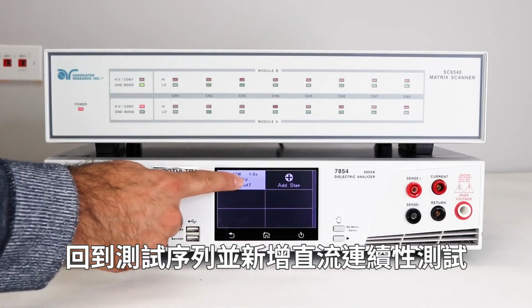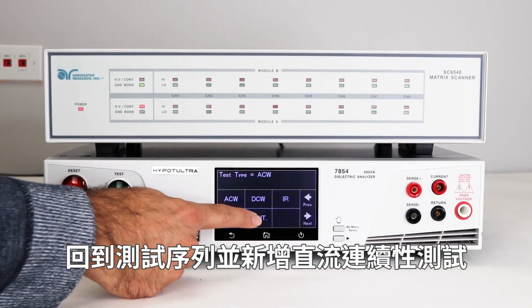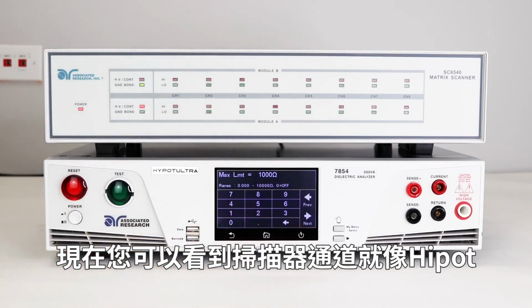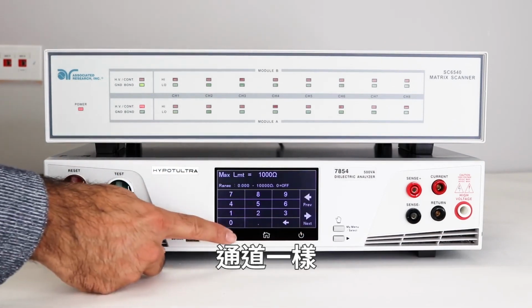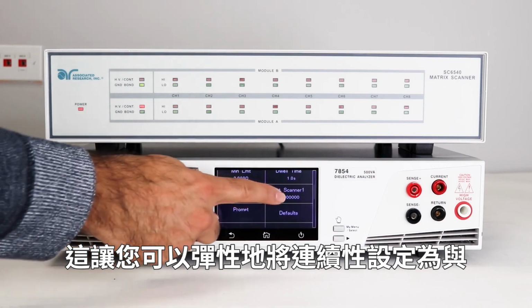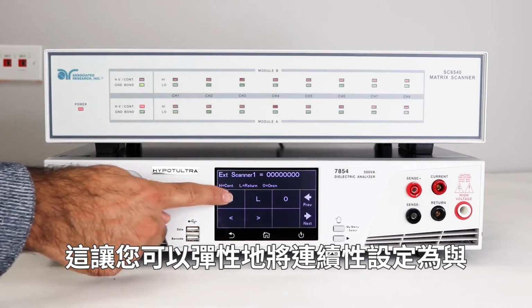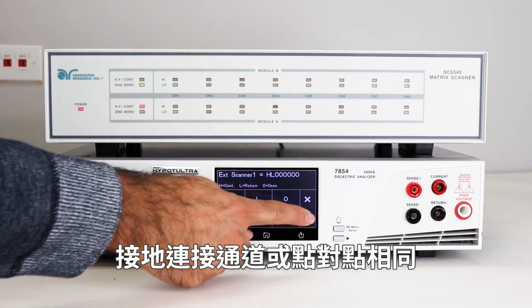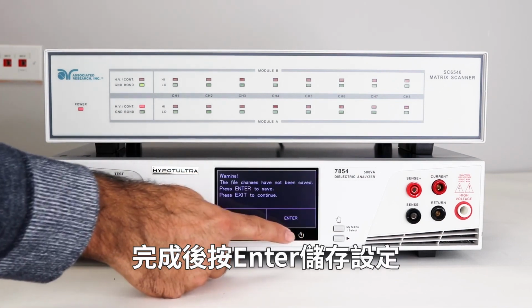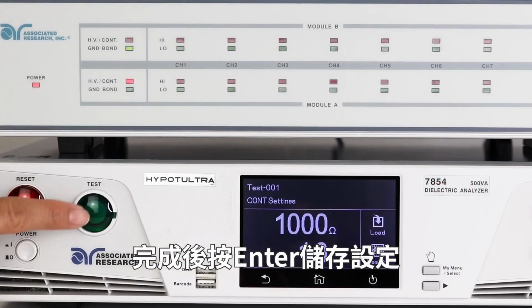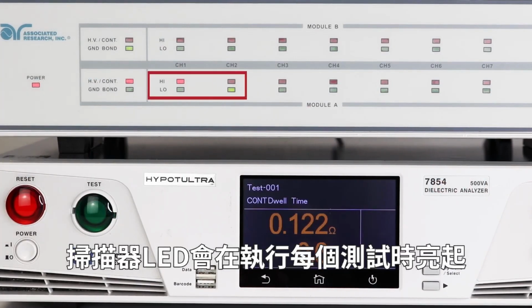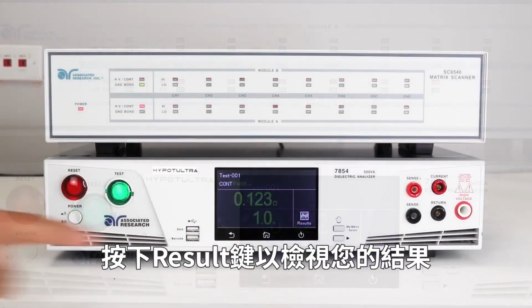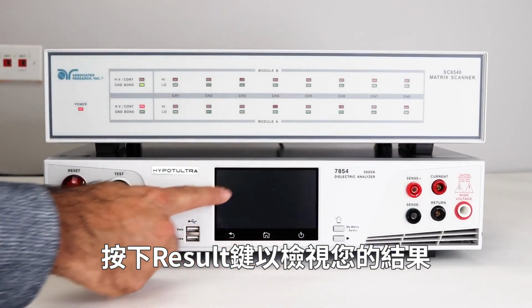Go back to the test sequence and add a DC continuity test. Now, you can see the scanner channels just like the HypotULTRA channels. This gives you the flexibility to set continuity either the same as ground bond channels or point to point. Once completed, hit Enter to save the setup. Press the Test button. The scanner LEDs will light up as each test is being run. Press the Results key to review your results.